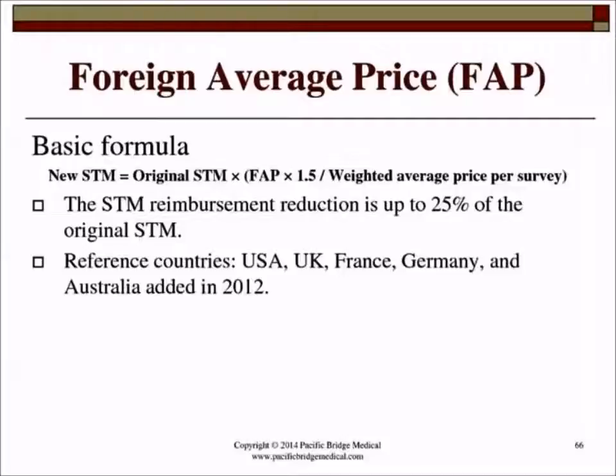Normally, this is a good example for companies. You have a product which has some new features, and the question is, should you put it in an existing category, like a category B, which is going to give you a little lower reimbursement, but you can get the product on the market sooner, or should you push for a little higher reimbursement, which will take more time to get and will delay getting the product on the market? And keep in mind that in Japan, it's very difficult to change the reimbursement once the product reimbursement code has been allocated. So it's not like you can go for a category B reimbursement now, get the product on the market, and then later think it's going to be easy to go to a C reimbursement category. I think to switch from a B to C oftentimes will require restarting the reimbursement process.